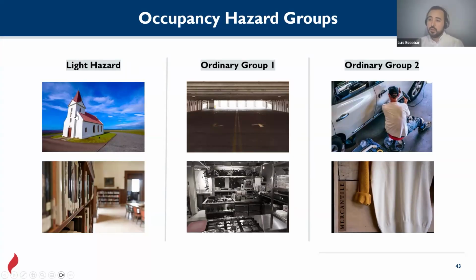So, I'm sorry, a church is an occupancy that has limited combustible materials. It can be a library, which, even though we have books and combustible material, the heat released by those combustibles is not high enough to consider a life-threatening issue compared to the heat release in other applications. Don't get me wrong, these two are important as well, but the heat released is not the same as, let's say, a mechanical shop, where we have oils, solvents, and all those materials that take a lot to consume, and the heat release for those materials is way higher than a paper sheet.